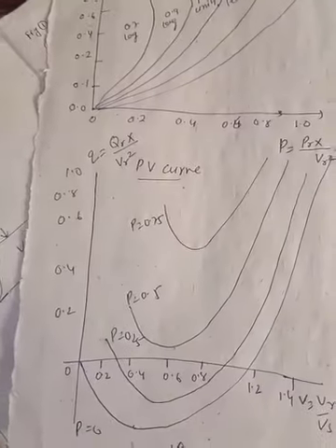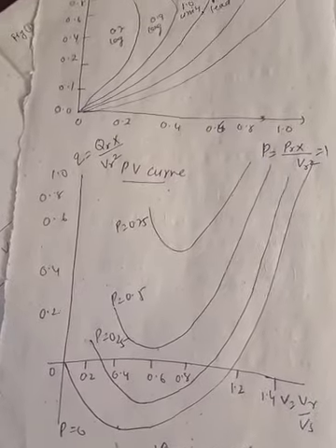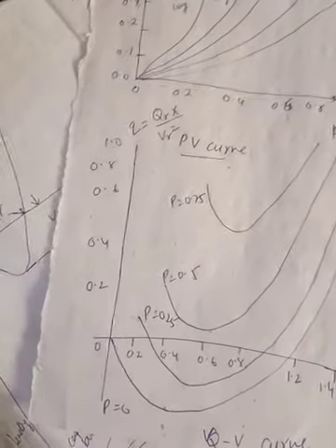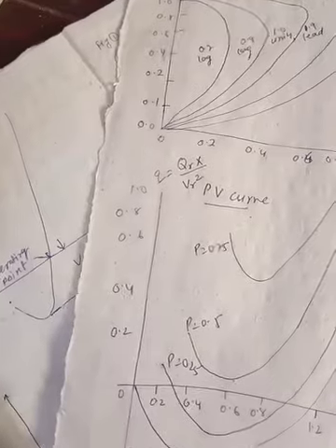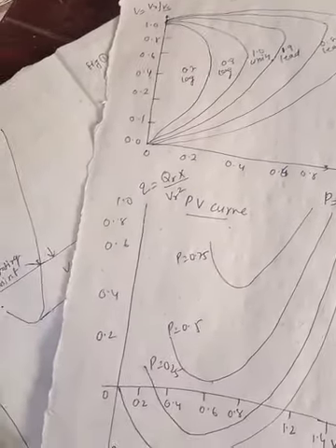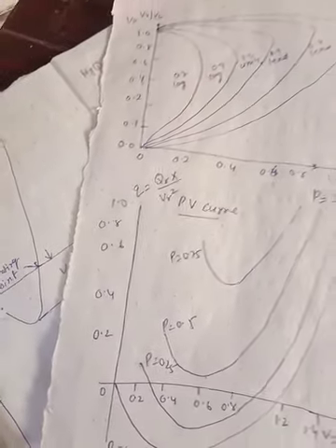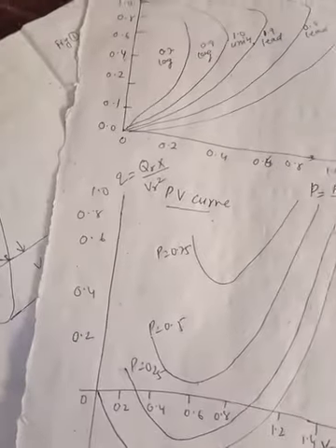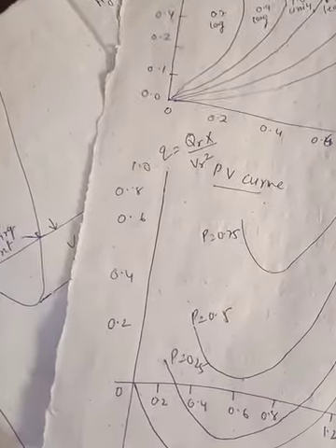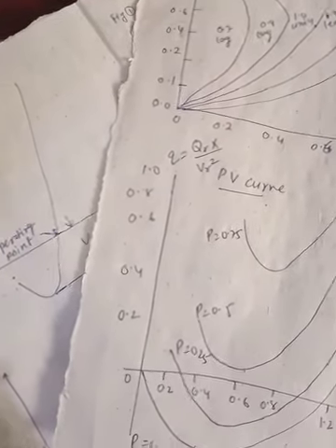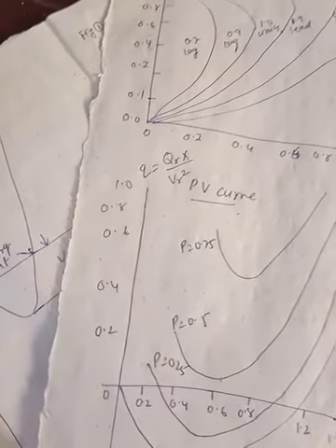So we can say that when we are talking about the PV curve, it is necessary to convert the system into a two bus system, but in case of the VQ curve method, there is no need to do so. Voltage at a test bus or critical bus is plotted against the reactive power at that bus. A fictitious synchronous generator with zero active power and no reactive power limit is connected to the test bus, and the power flow program is run for a range of specified voltages with the test bus treated as a generator bus.